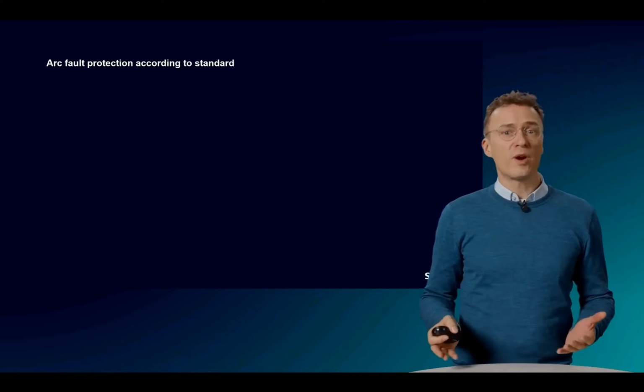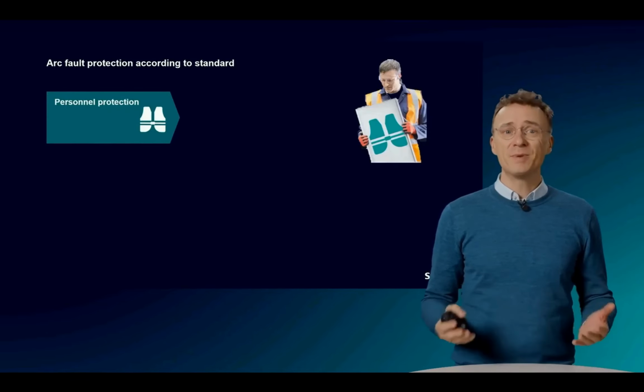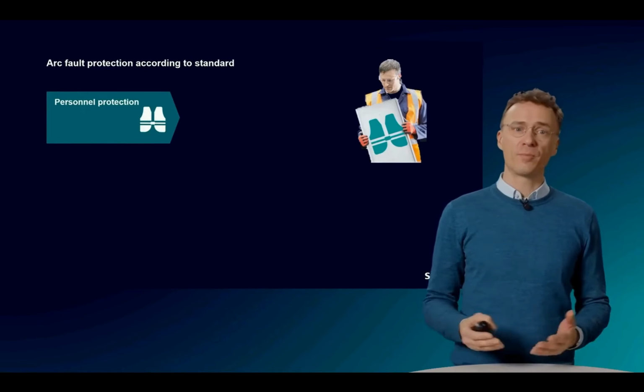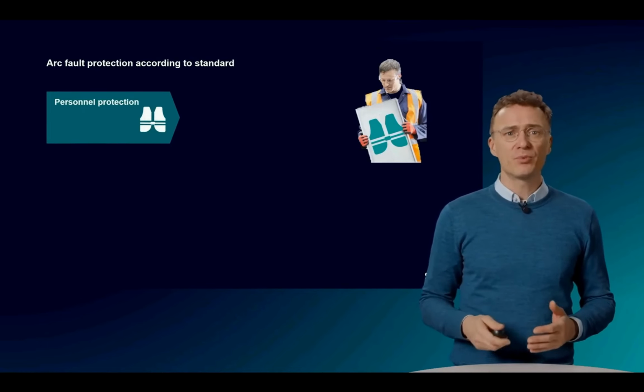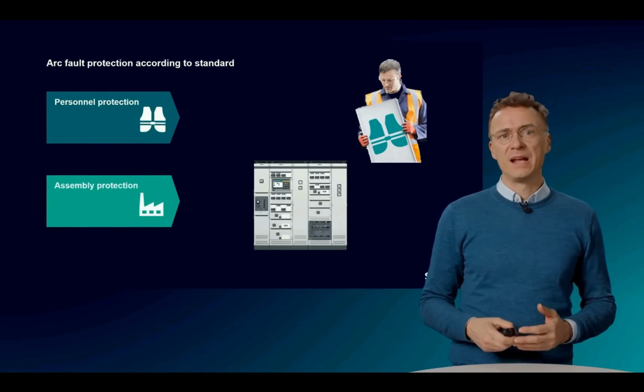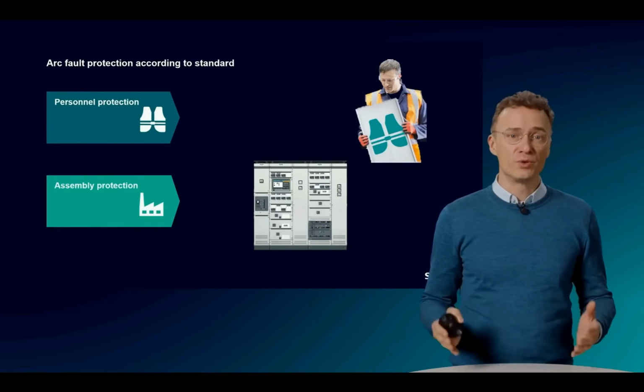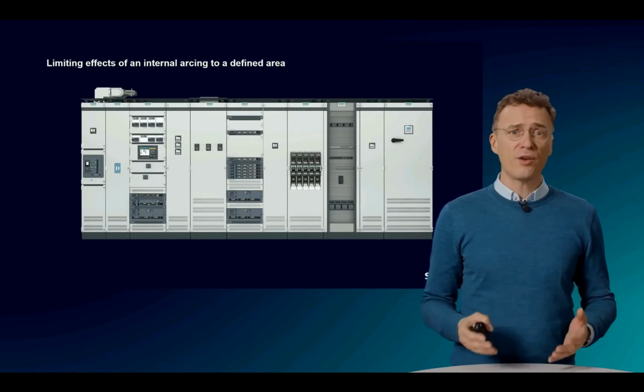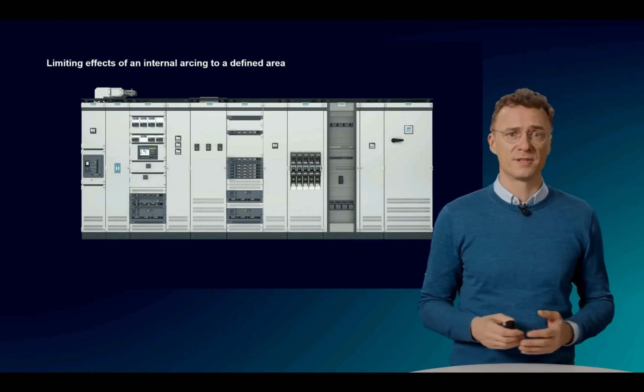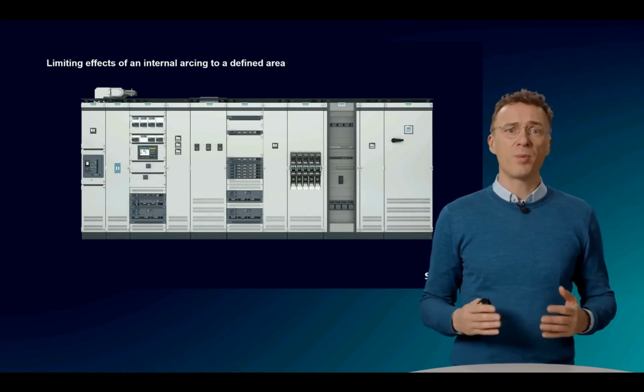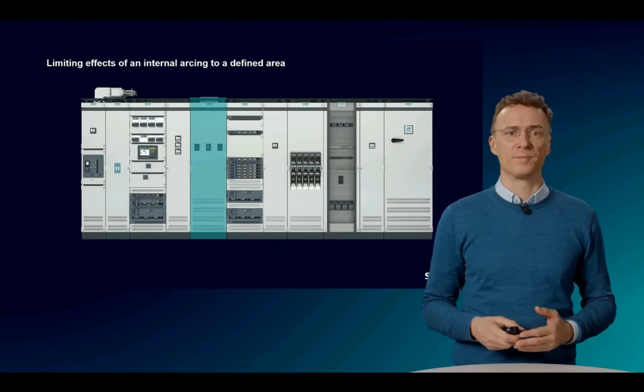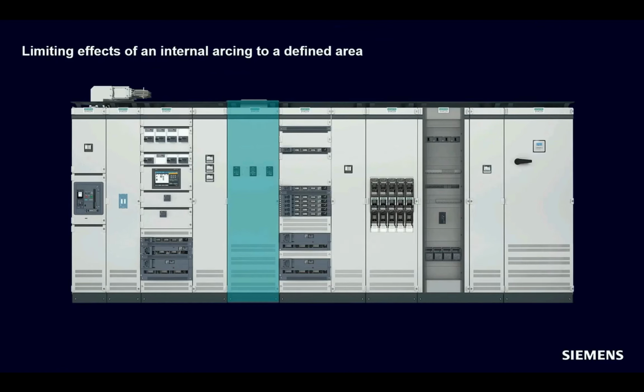Here, the minimum requirement would be personal protection. This means that a person standing in front of the system will not be harmed. In addition, system protection can also be achieved. And this is important for avoiding or reducing downtime. The effects of the arc fault are then limited to a defined part of the system. For example, a defined part can be a cubicle of the switchboard. This would then have to be replaced after the event. Or you can narrow down the area further to one compartment. In this case, only the compartment with the withdrawable unit would have to be replaced in a system in withdrawable design.